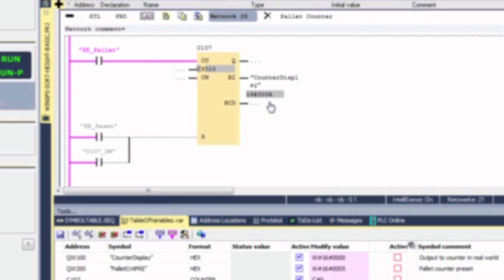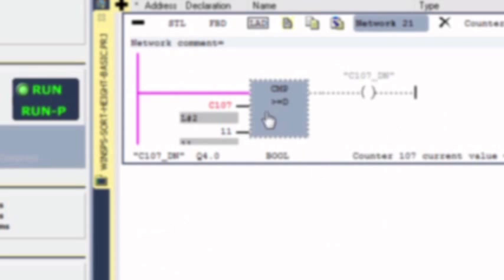When the counter gets to 11, it resets to 0 automatically. That fires the done bit when it reaches 11 from the compare statement. Right now the current value in the counter is 3 and the preset is 11. So when this current value reaches 11, the output becomes true — that in turn causes rung 20 to become true and resets the counter to 0. So that's a closer look at the counter.